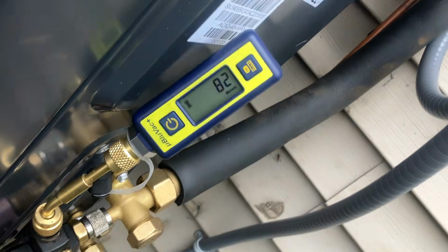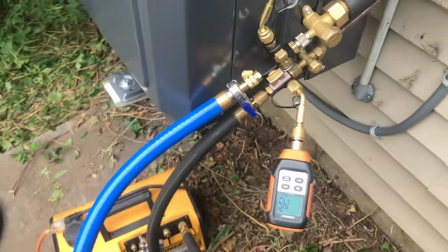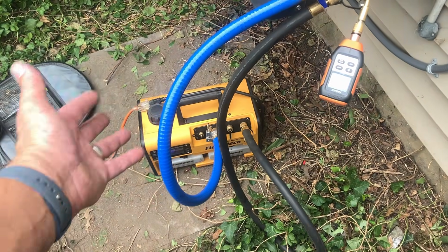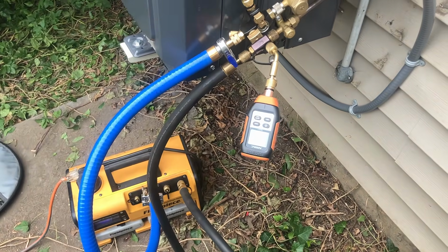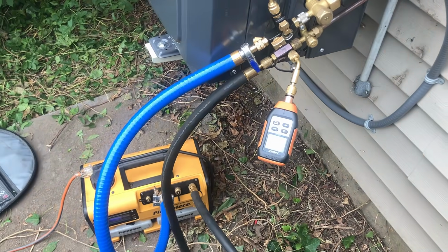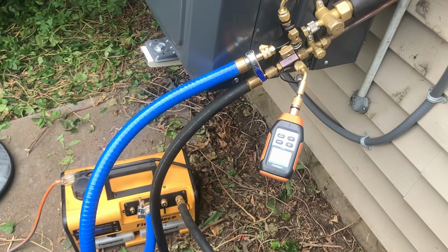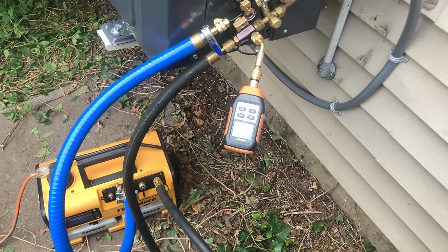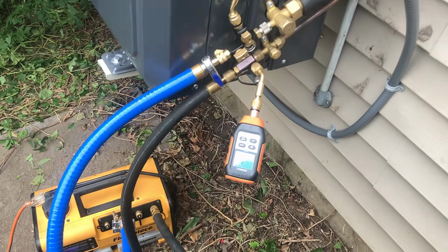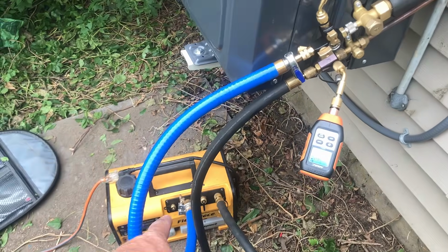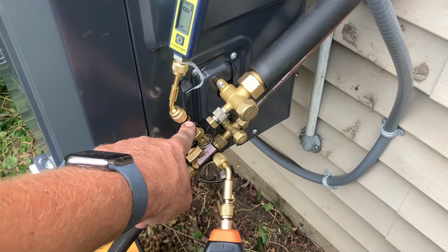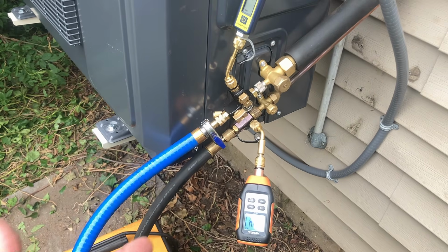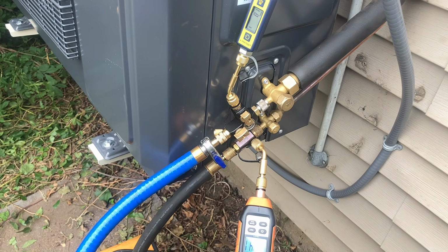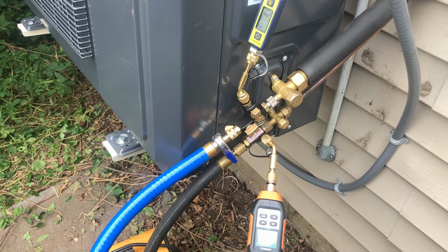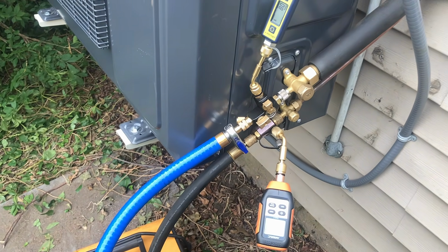146, 82. I don't really know if this is a faster process using 2 hoses, but I have 2 micron gauges and I like to compare, see which one's better. I have the ACiQ tools on the 3/4 inch line, and the Appion hose with the Navic micron gauge on the 3/8. I don't know what's better, but I like the ACiQ tools. I like the Fieldpiece Schrader core removal tool. I had to throw one out yesterday because it was leaking. It's annoying, it's only about a year old, but I don't know, this equipment, tools you use, especially dealing with the vacuum process, doesn't really last that long. It just don't.